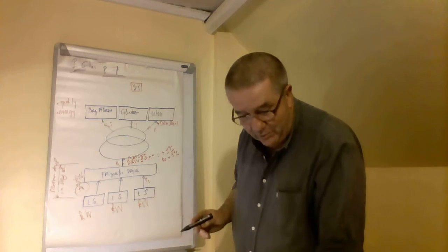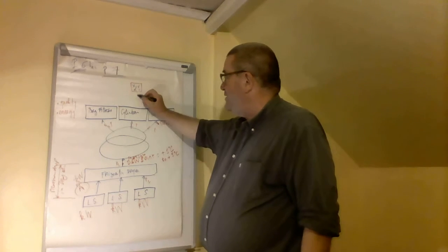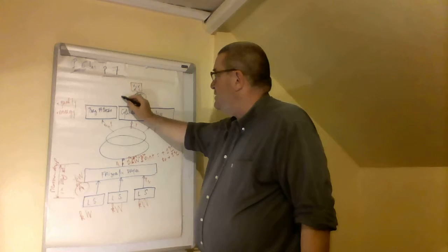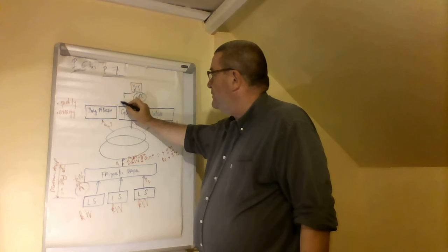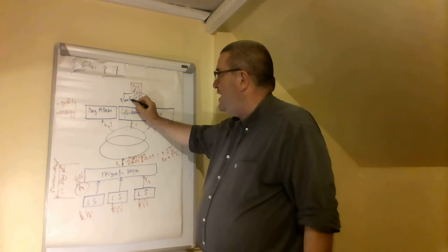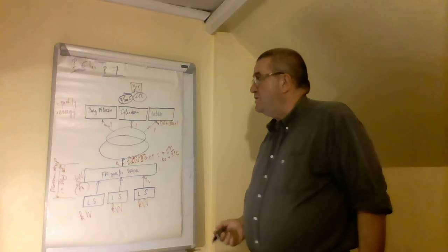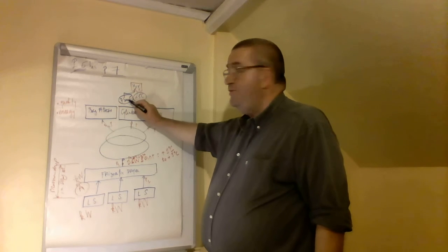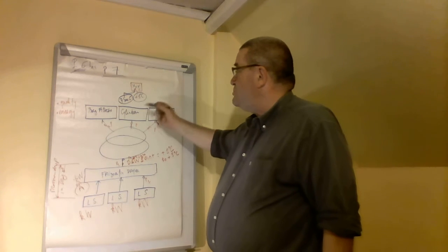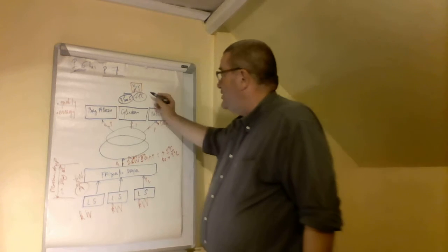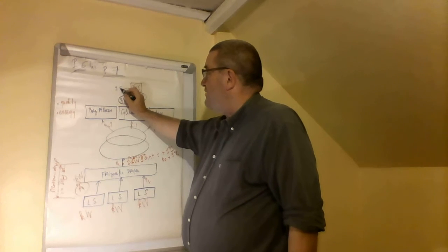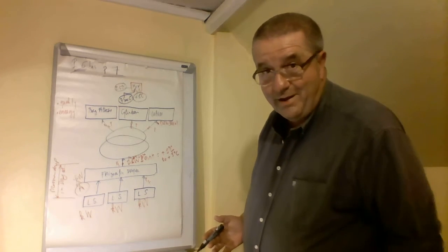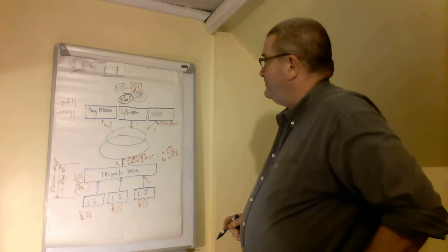So what happens if you decide to measure? Maybe you measure here and you see that you have +1 Celsius, and you have also, at the same time, 7 bar gauge. This is the measurement. You have always to measure at the same time the pressure dew point, the dew point, and the pressure at which you measure it. And as you want to make complete work, you can also measure here the fact that you are at 25 Celsius. We are in summer in France, and today the temperature was 25 Celsius in my region.